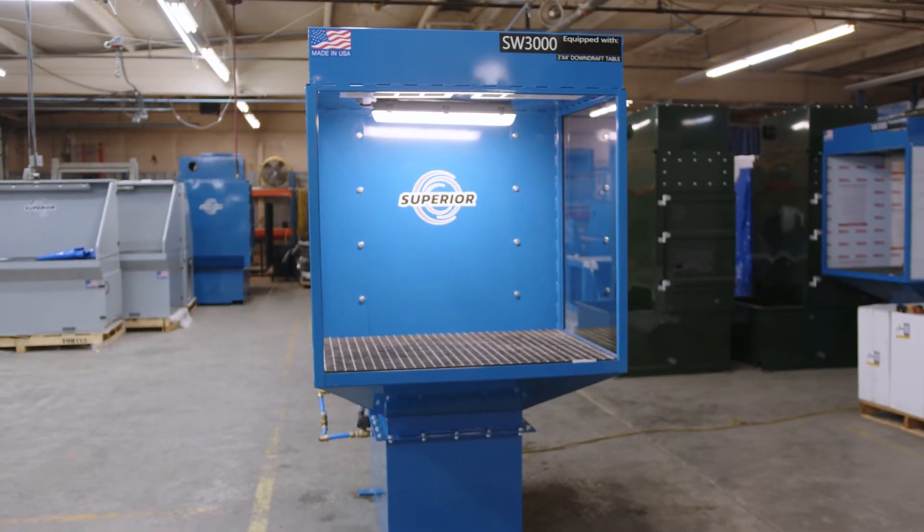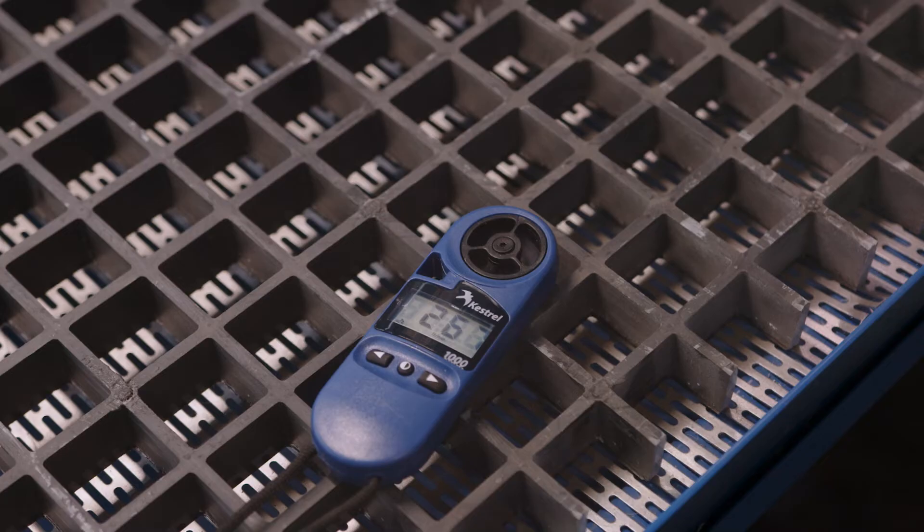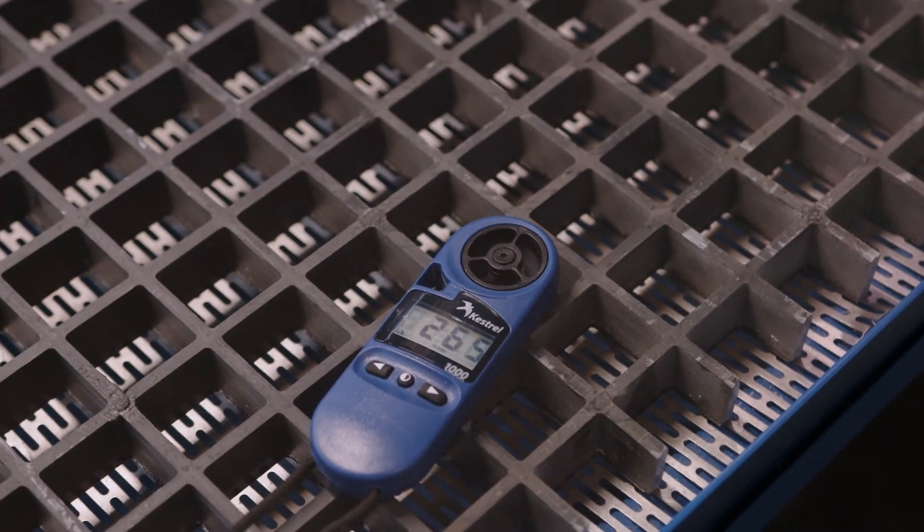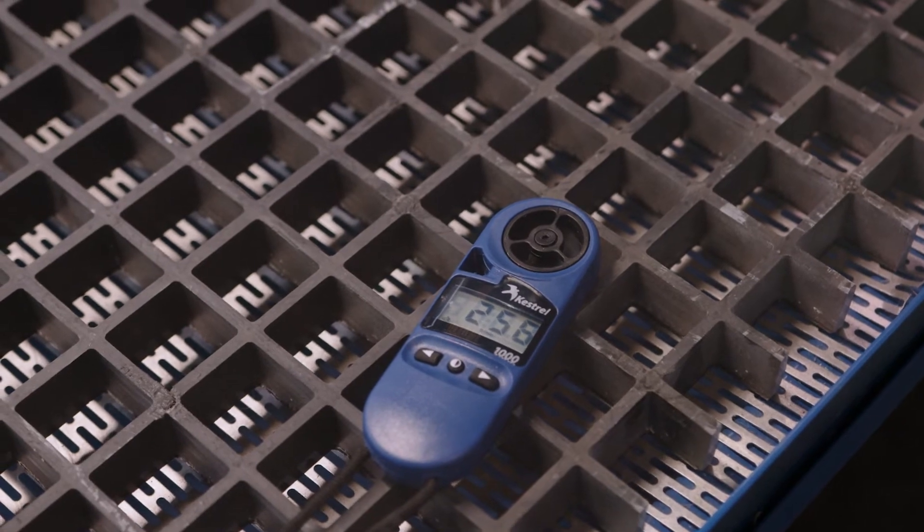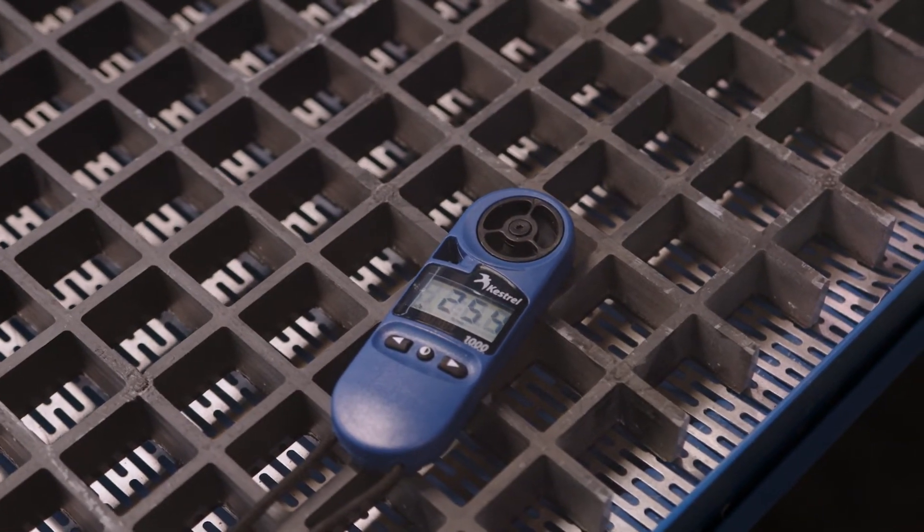If your unit is a downdraft table, it is designed to operate at a minimum of 250 feet per minute of downdraft suction. This can be measured at the table surface and is noted on our quality control check sheet when it's shipped from our factory.